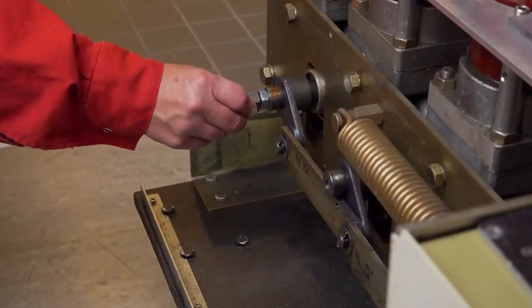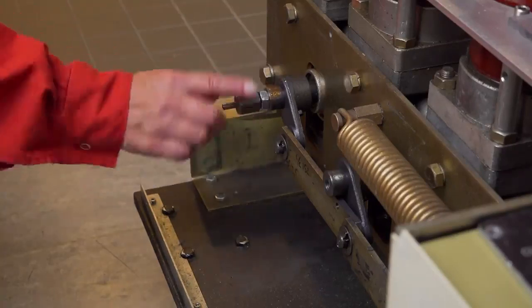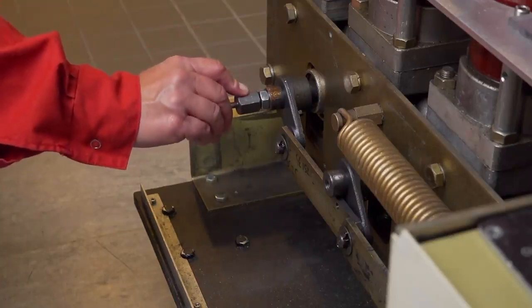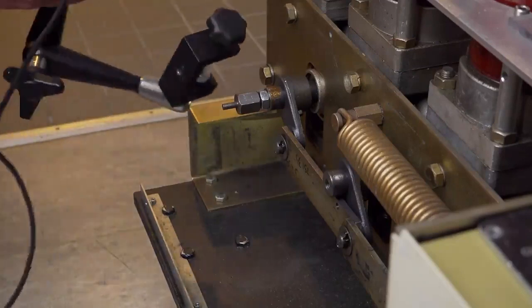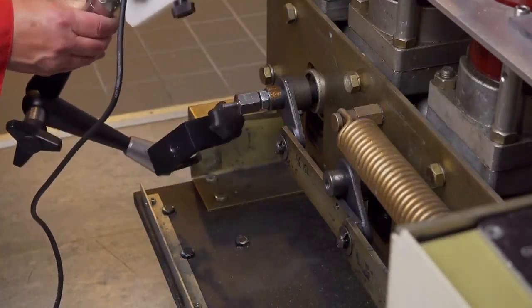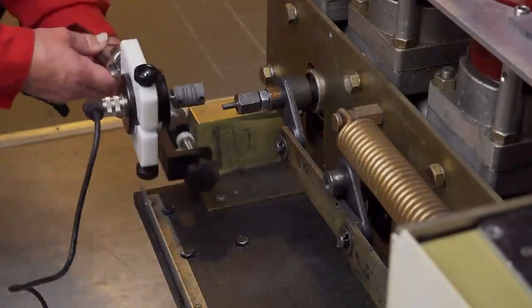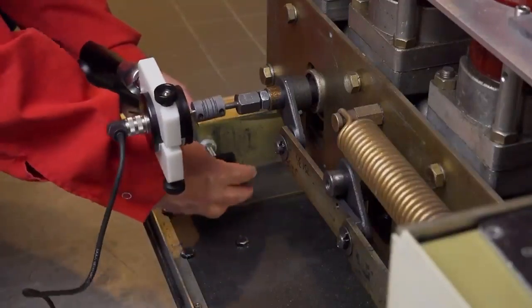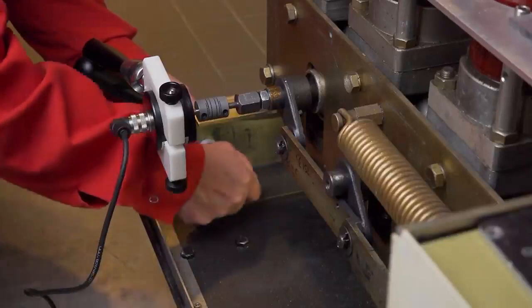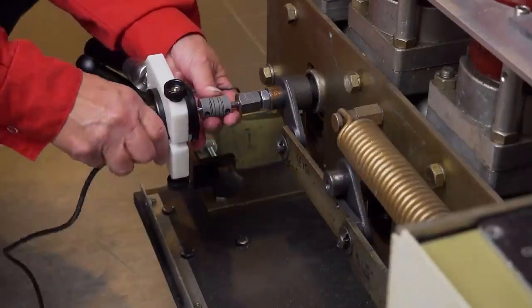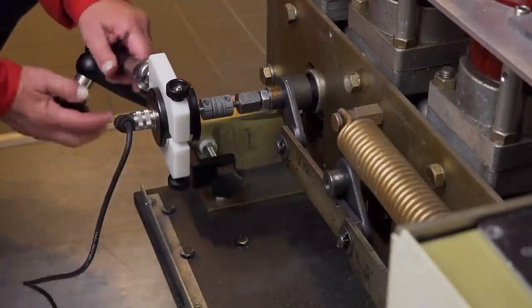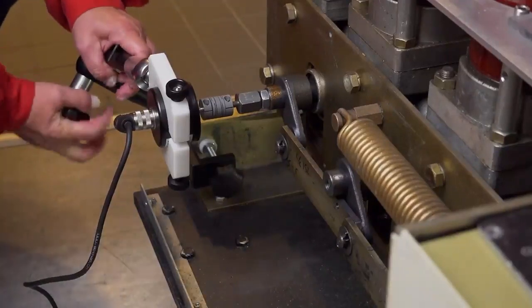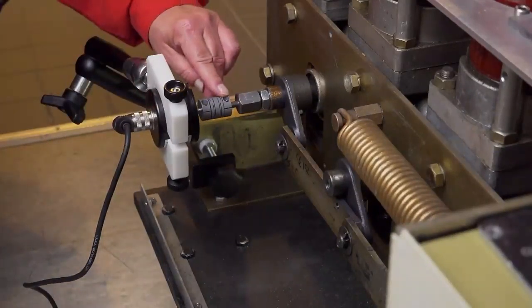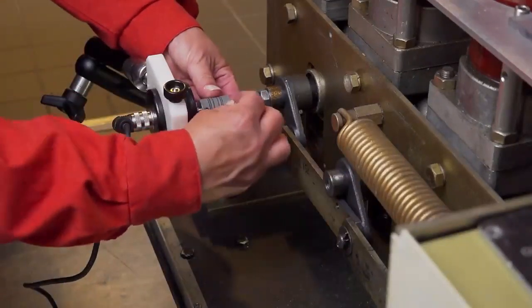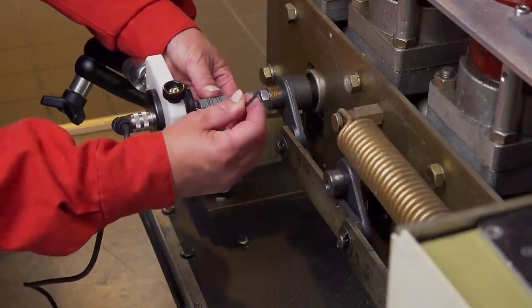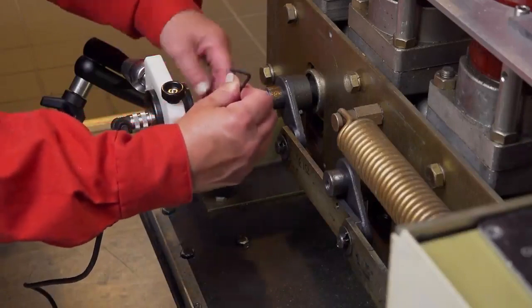I have connected a part from the rotary kit on a rotating point in the mechanism. This rotating point reflects the motion of a pole. I have prepared the angle so I can easily connect the transducer. I need to connect it steady with a C-clamp and adjust the angle so it's aligned properly and steady. And I have to connect and adjust the flex coupler.